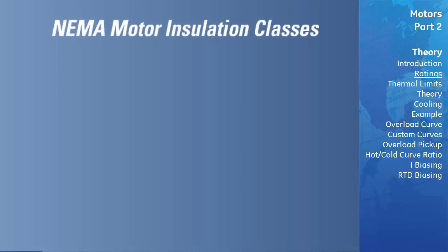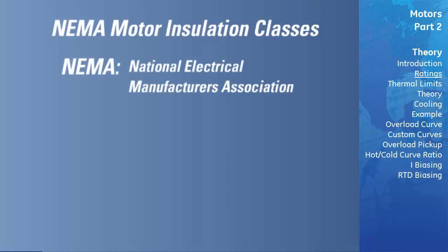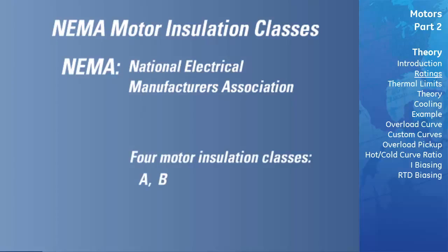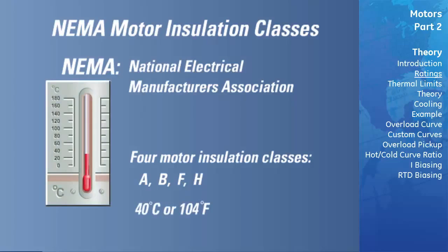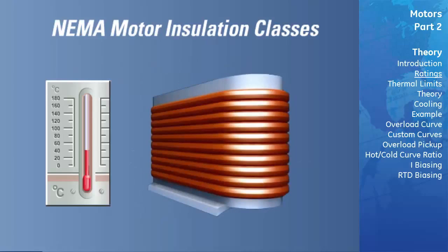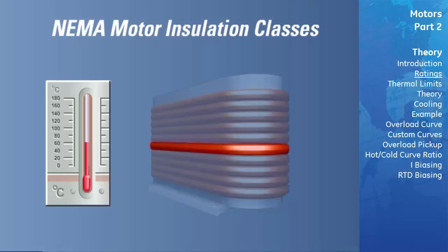NEMA Motor Insulation Classes. NEMA, the National Electrical Manufacturers Association, has established four motor insulation classes: A, B, F, and H. The specification has standardized on an ambient temperature of 40 degrees Celsius, or 104 degrees Fahrenheit, for all classes. Each class of insulation has a different maximum motor winding temperature rise, in addition to a hot spot temperature, which is an additional temperature rise for the windings that are surrounded by other windings.